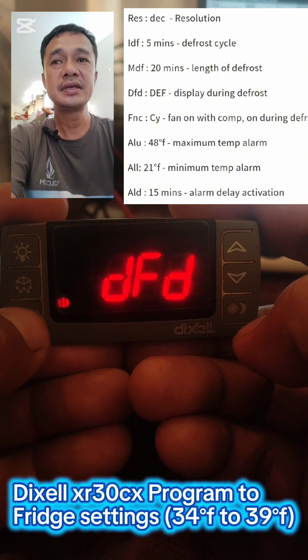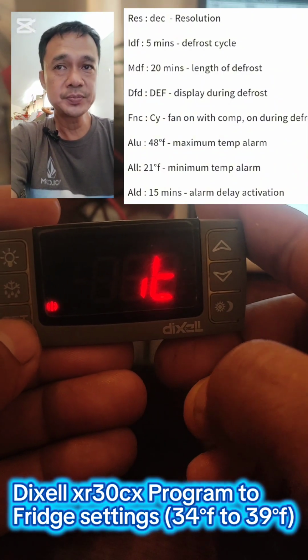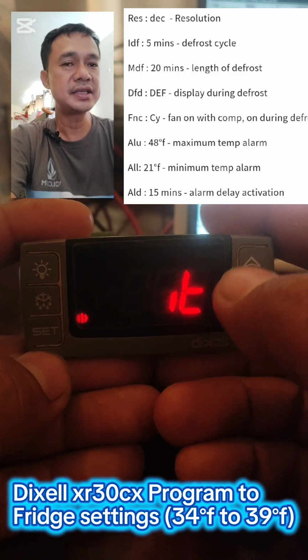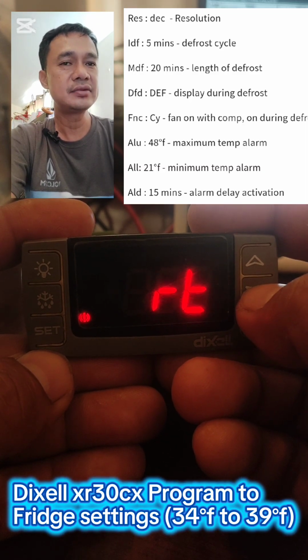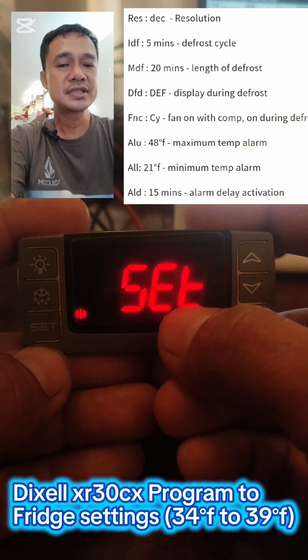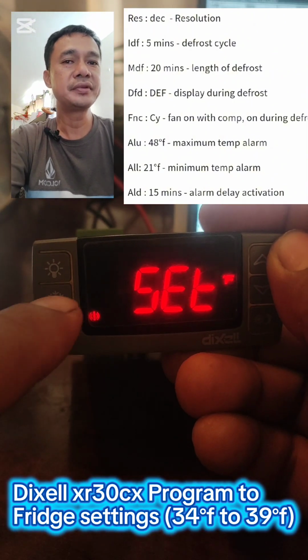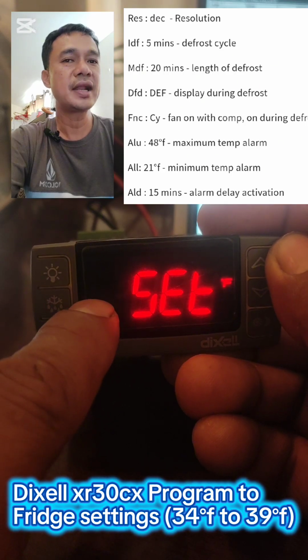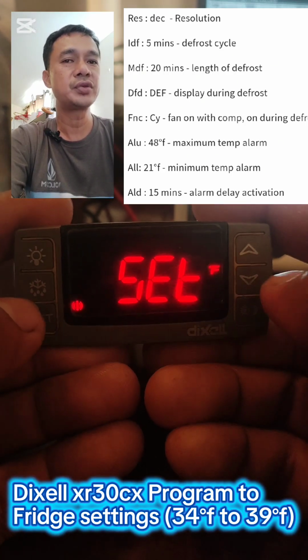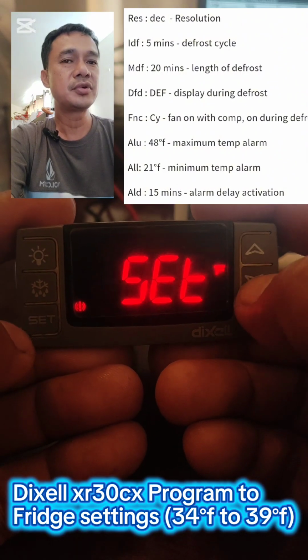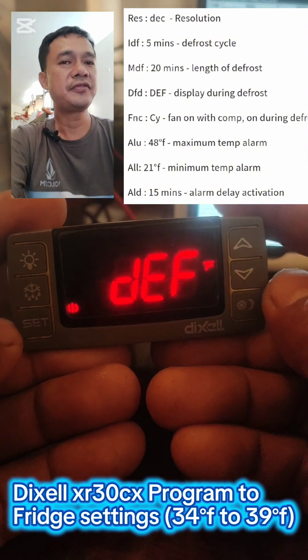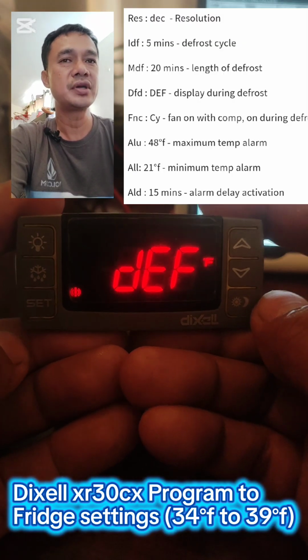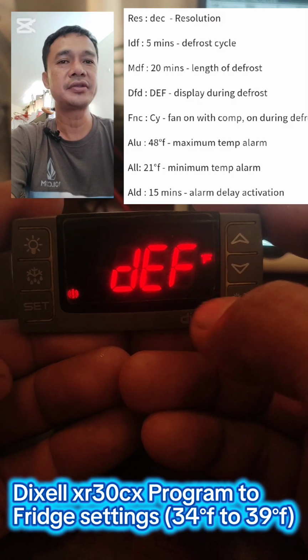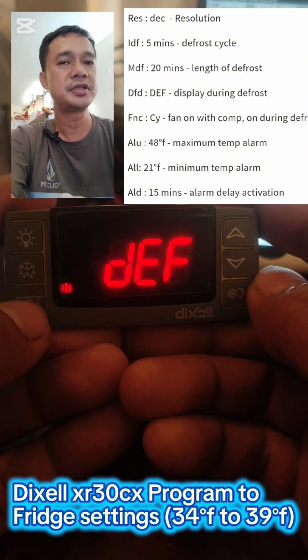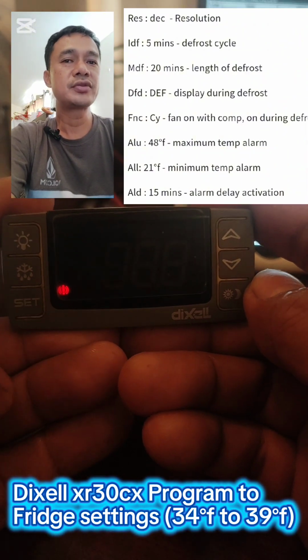Then DFD stands for display during defrost. IT, don't use that. RT, do not use that. For example, a defrost happened, the defrost light indicator here lights up, and your set point is 34. It will appear 34 during the defrost, but I'm going to select DEF. Alright, for this DEF, just in case you have an internal auditor or external auditor, if they see the unit is in defrost, they are not going to question you. Then proceed to memorize. That is ideal.